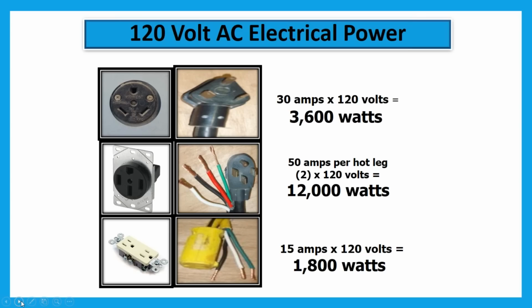Now some of us are maybe staying with someone and using an extension cord that we're plugging into. These extension cords are typically a little lighter weight, and what we typically see on those is 1,800 watts. That's half of what that 30 amp is producing, because a lot of folks will take that 30 amp power cord, put a reducer on it, stick it onto an extension cord, run it across the yard, and plug it into somebody's wall receptacle in their garage, some kids or friends you're visiting. You think you're getting the full power that cord is designed for, but you're not, because that extension cord is choking it down.